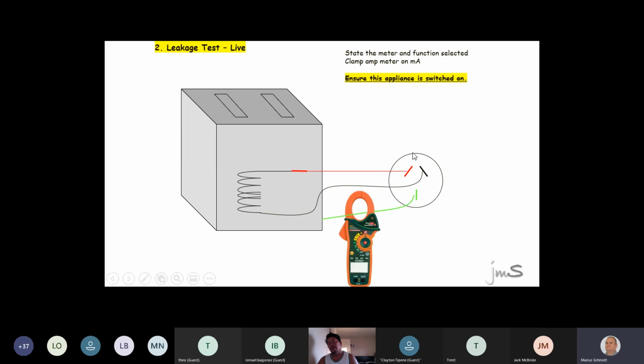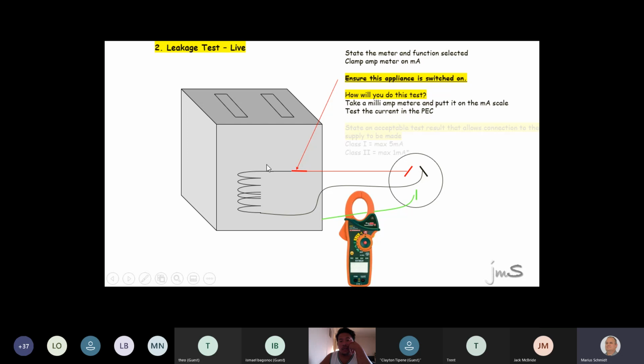If I give you a class 1 appliance, all readings will be 5 milliamps or less. The current. Sorry, a clamp meter. Class 1 means there's an earth connected. The class 1 cannot be greater than 5 milliamps, the leakage current. If I give you a class 2 double insulated one and you put it in the sink top, you plug it in, and you measure the current in the earth, it shall not be greater than 1 milliamp. Now guys, I know for a fact that has been asked in the exams before. So what is the maximum current allowed to flow in a class 1's earth? 5 milliamps.